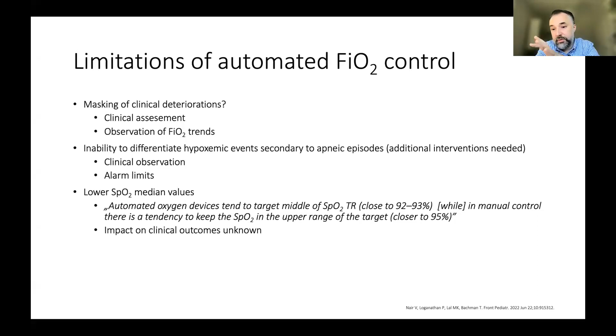And there are also observations that with the automated oxygen, the devices tend to target middle range of SpO2, while in the manual control, there is a tendency to keep the SpO2 values in the upper range of the target. However, what is the clinical significance of this, we don't know. There are some technical problems. One of the issues that, for example, we had in my unit is that sometimes we would see differences in the SpO2 values between the values on the ventilator and on the main monitor, which can be difficult to interpret, and we may feel uneasy which value you should follow.